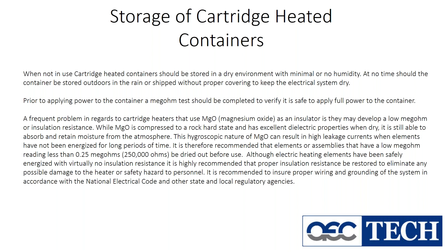If not, as soon as you put power to it, bang, you're going to blow the elements out. So you need to preheat those, either in an oven with no power to them until you dry them out, and then you can slowly draw them up. Simple practical method for the elements is to preheat them in an oven. Use your material heating oven if you like, but you're going to have to dry them out until you can get those ohm readings the way that they should be.